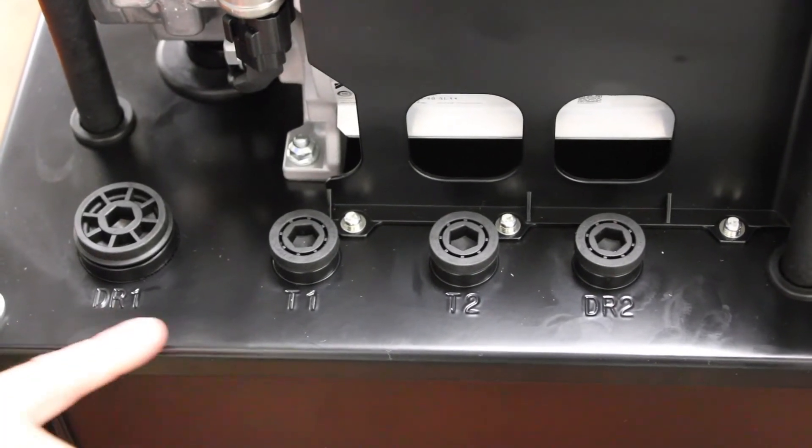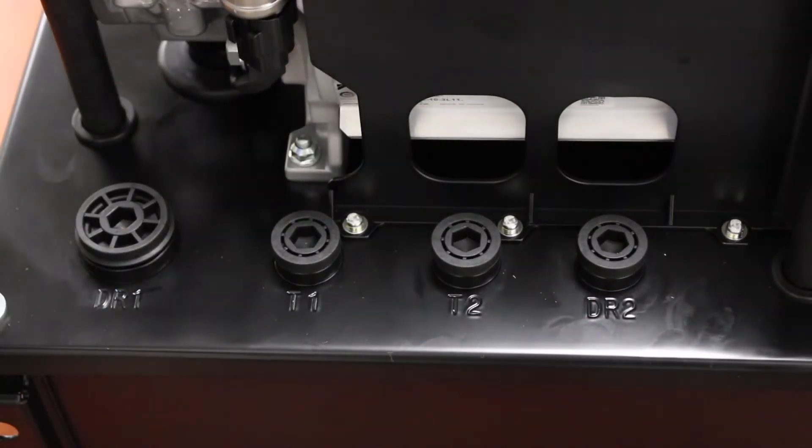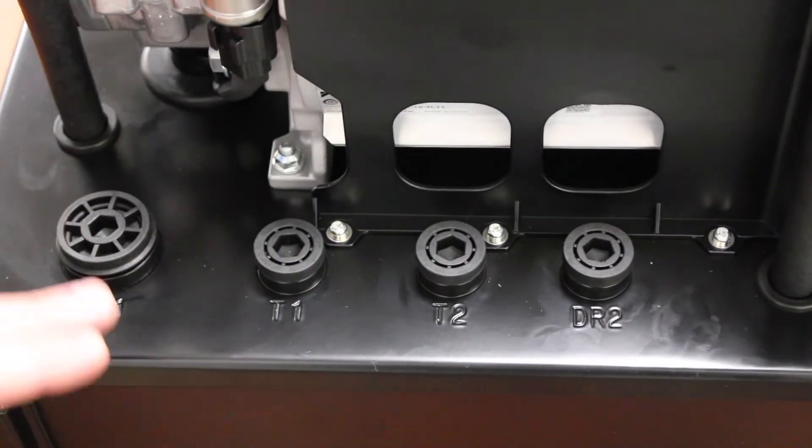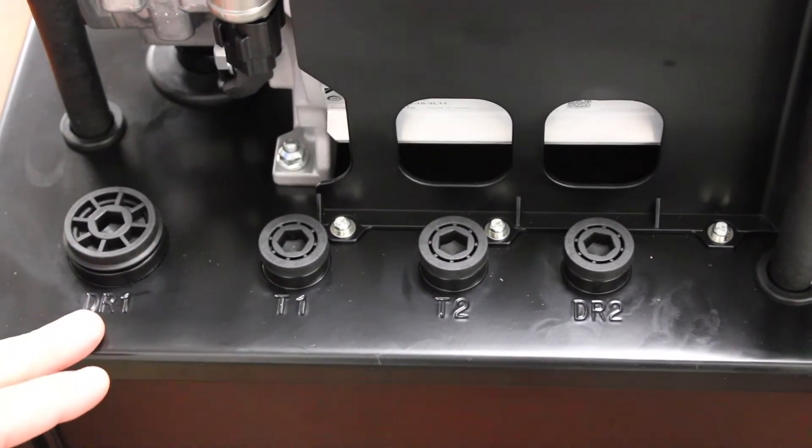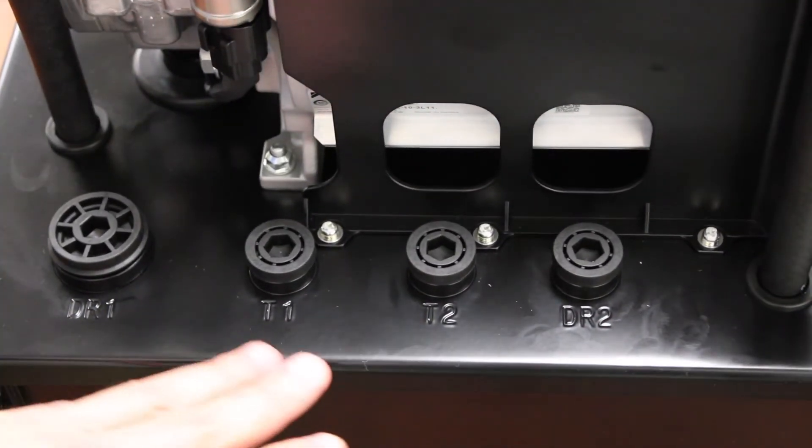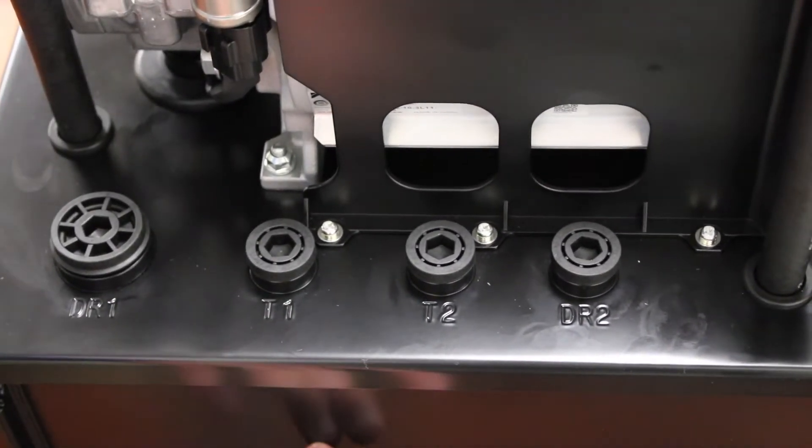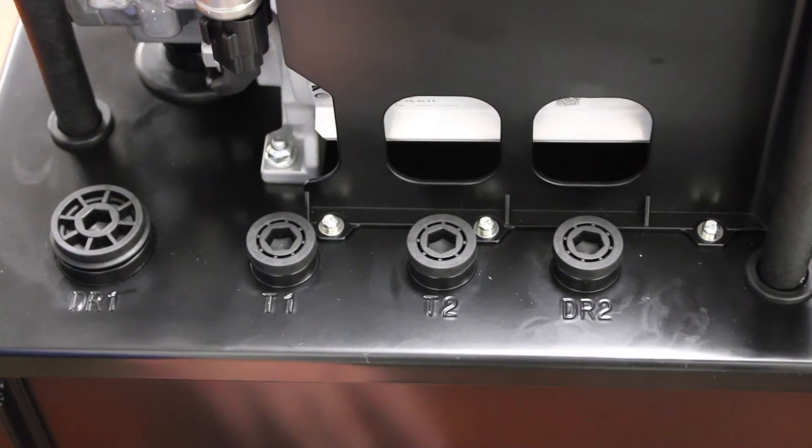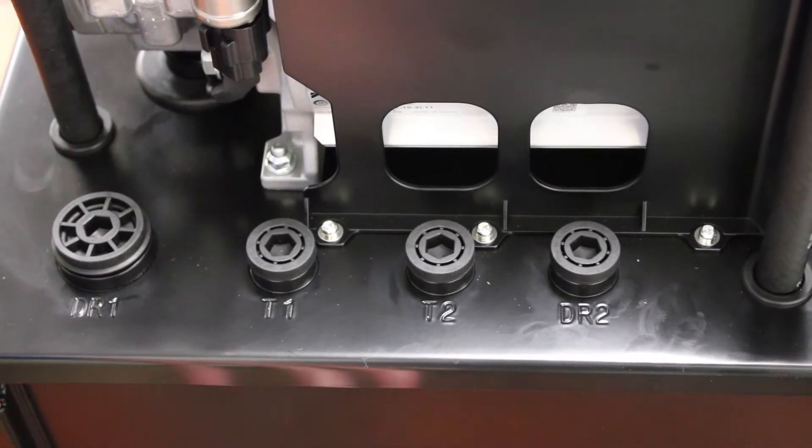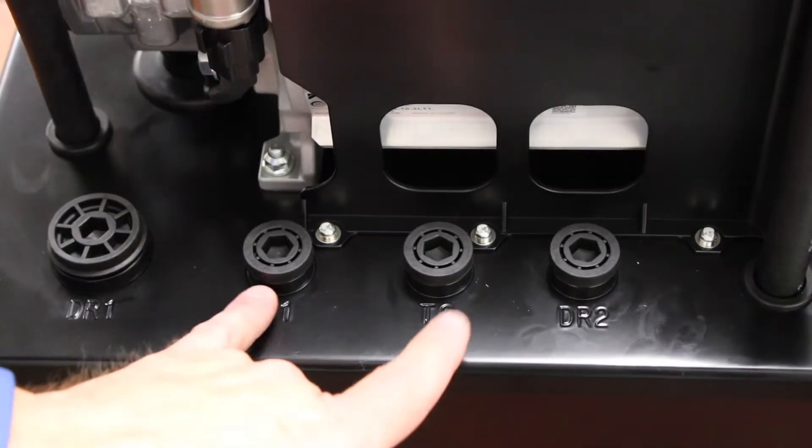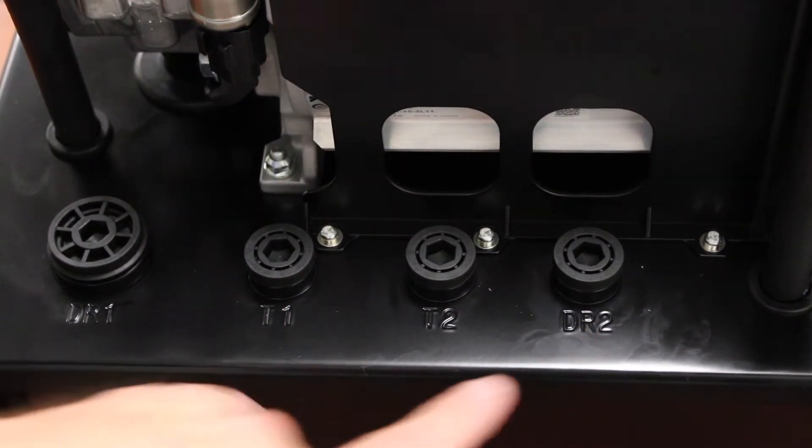When connecting your return line, you have multiple ports back here at the back of the tank. These three ports are half inch and this port is one inch. The difference between the drain ports being the outside two and the middle two on the tank are that the tank ports have a pipe inside that takes the oil down below tank level. This is important so we don't aerate the oil, so your return lines really should go here. The drain lines are for other applications.